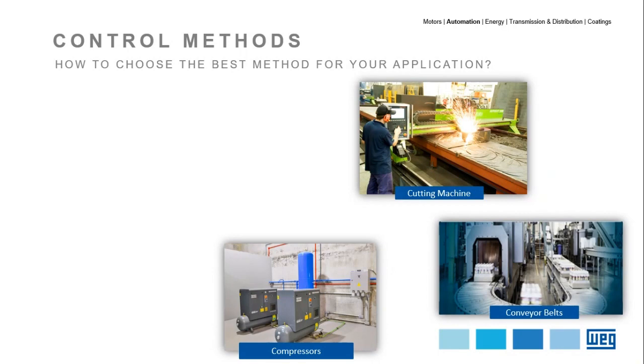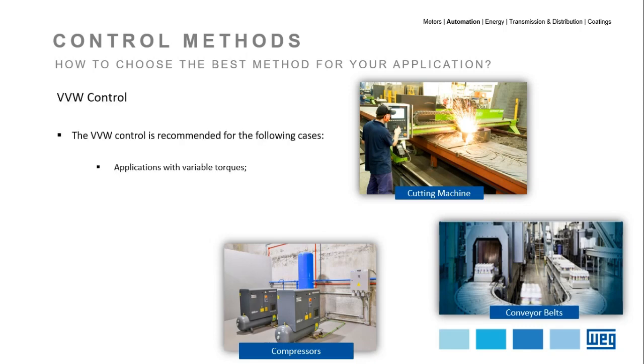For applications with some speed regulation or that start with load or heavy load variation, the VVW control is the most advantageous. It has a regulation of 1% of rated speed with a range of 1 to 30.